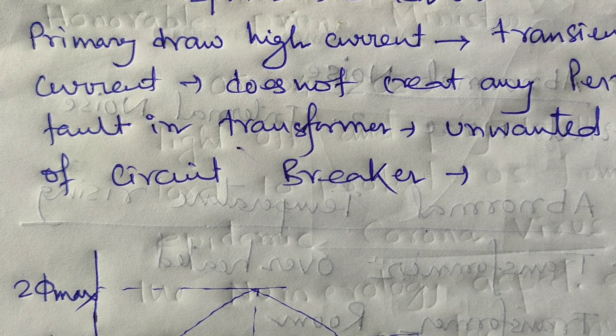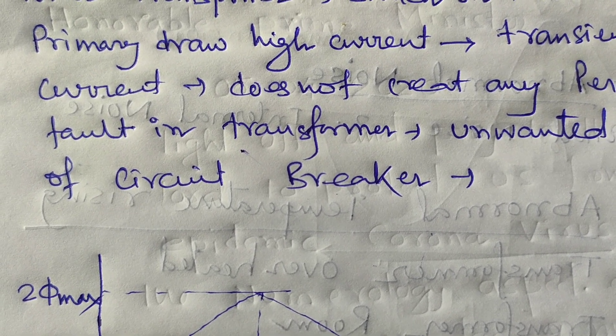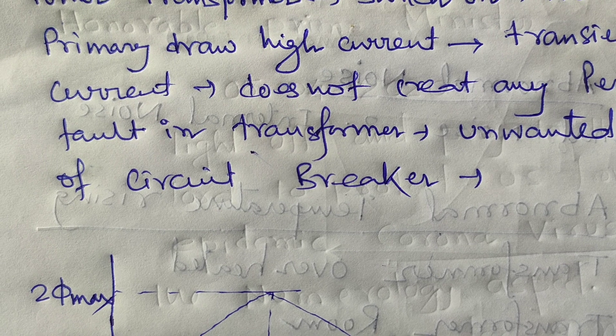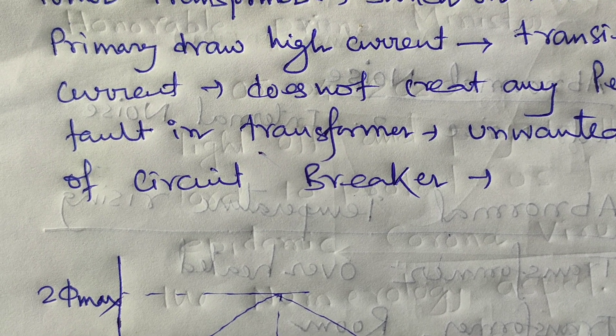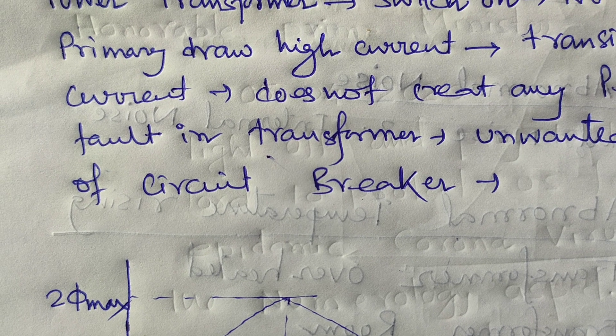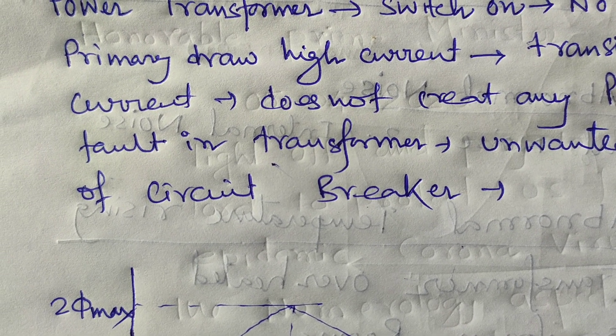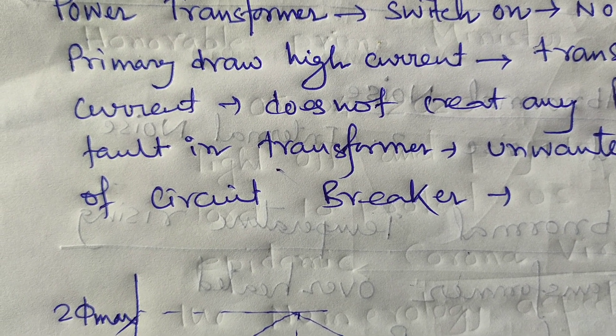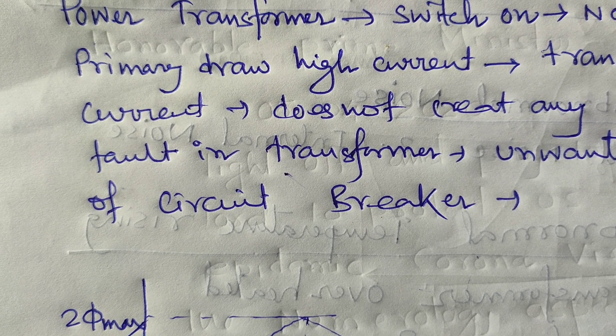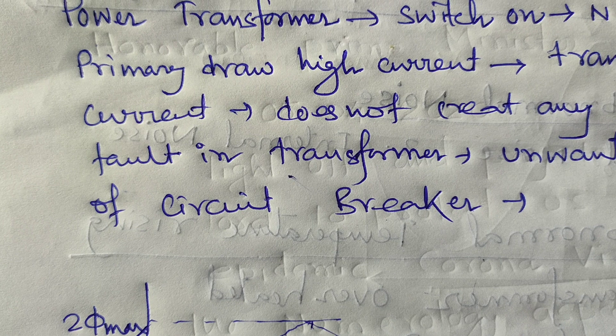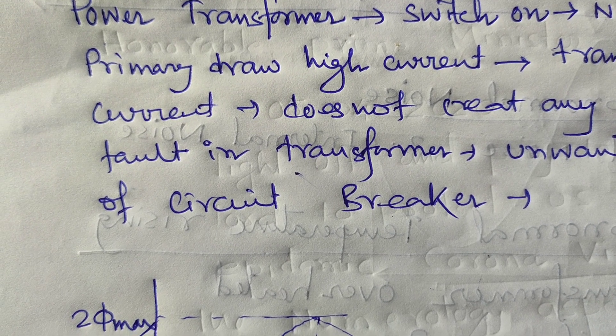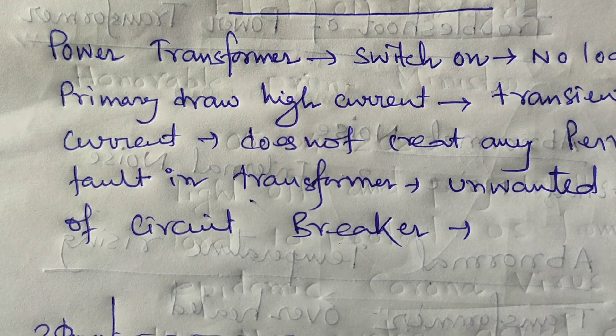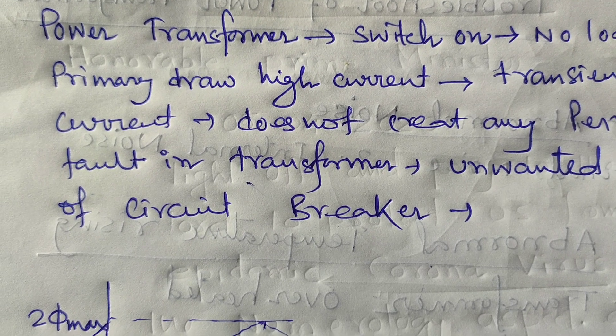This current can be as high as 20 times the steady-state current. Even though it only lasts for about 10 milliseconds, it takes between 30 to 40 cycles of current to stabilize to the normal operating value. If not limited, the high currents can damage the equipment, in addition to producing voltage dips in the supply line and causing malfunctioning of other equipment powered from the same supply.